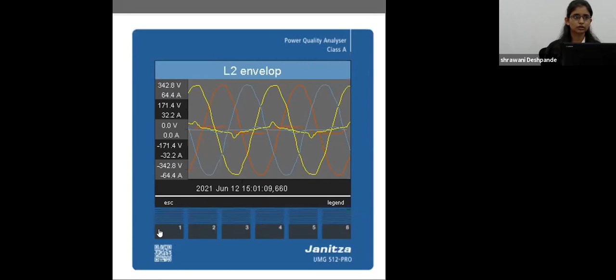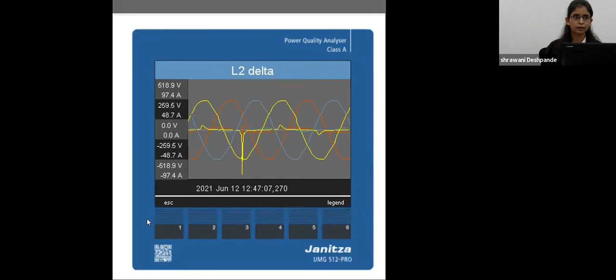Then transients. As I said, this meter has a sampling rate of 25.6 kilohertz. Therefore, it is capable of capturing transients greater than 39 microseconds. So we can see at which phase my transient has occurred, the type of the transient, and at what date and what time it occurred. If we select on this, we can see the graphical representation of the transient. Let's see the type delta. For example, if we select on this, we can see that my transient has occurred on the Y phase of the current waveform. Likewise, we can have a total of 18 values for the transient.